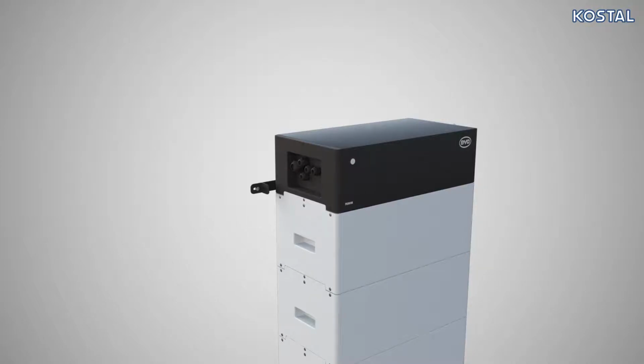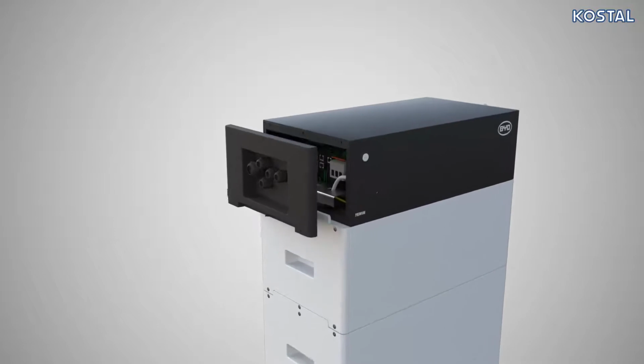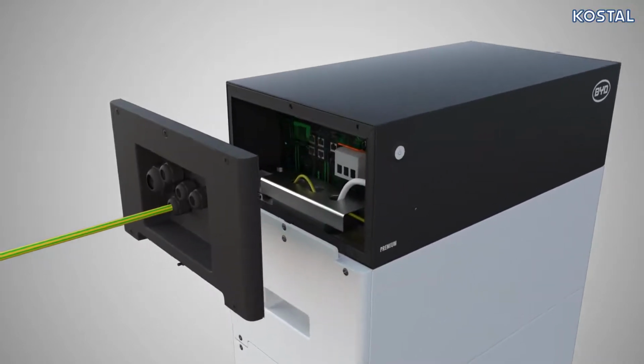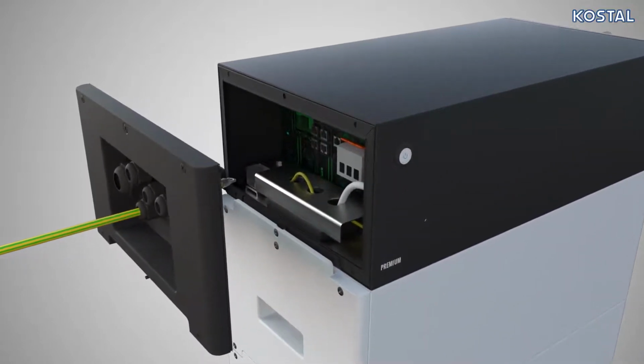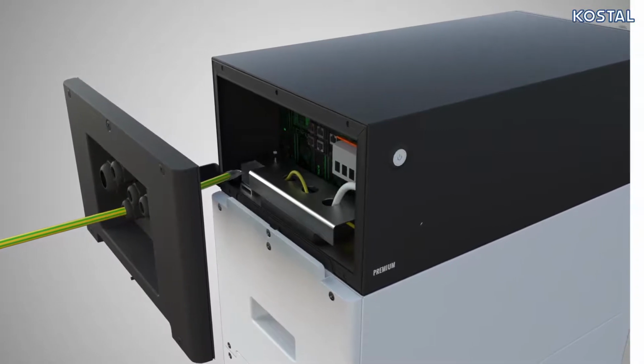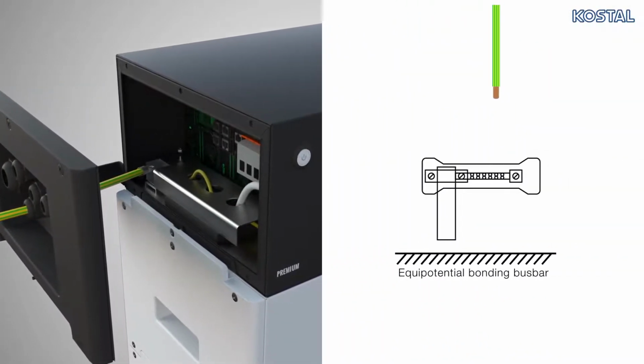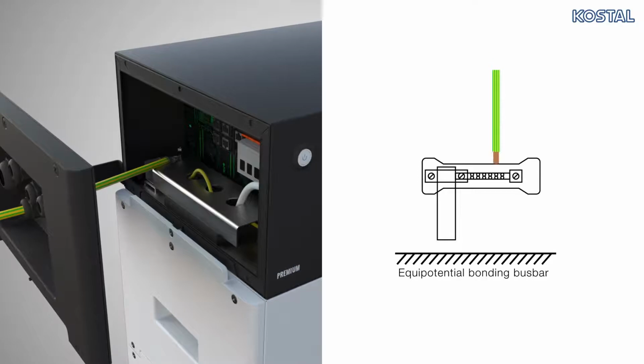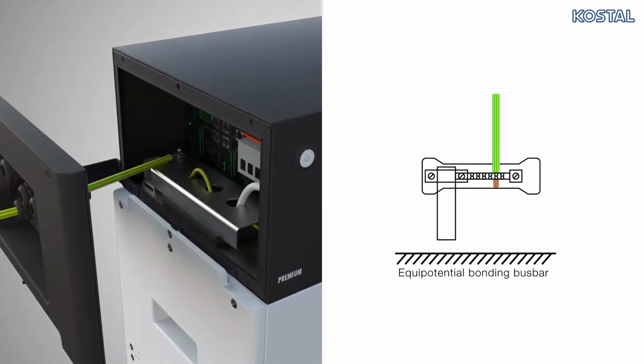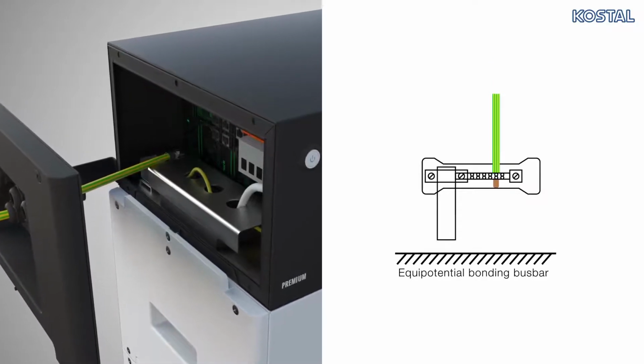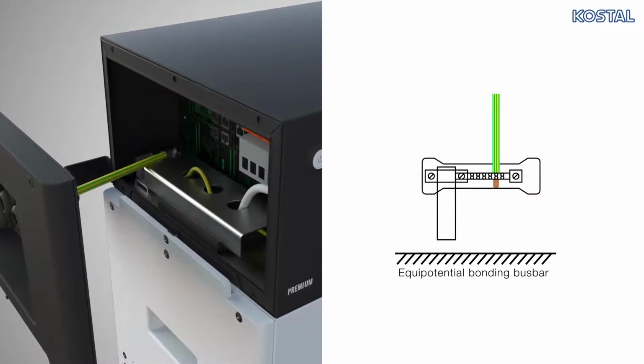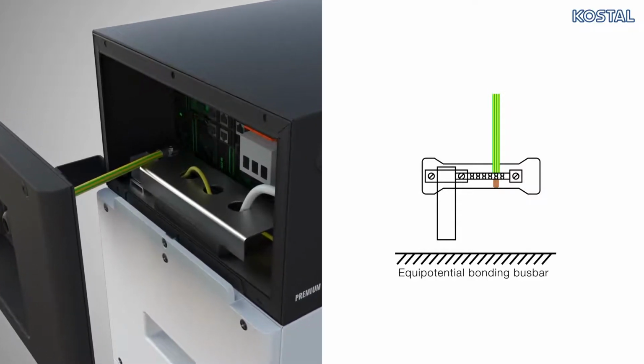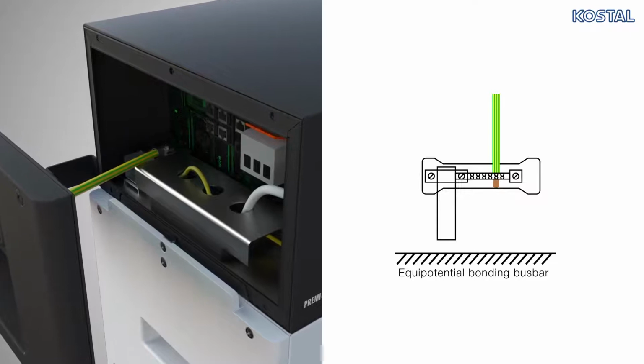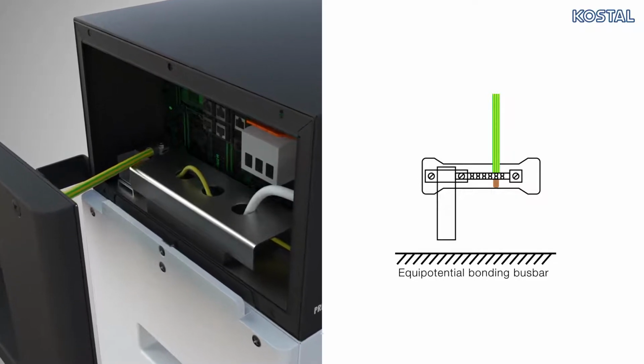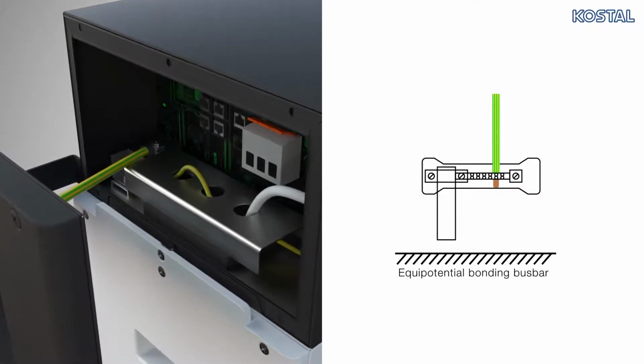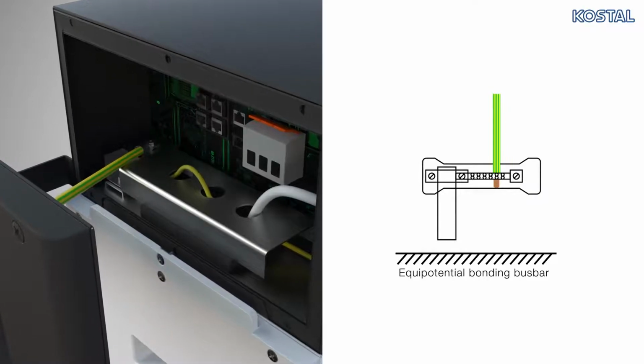Now guide the connection cables through the cable glands provided on the terminal compartment cover of the management module. Start by connecting the potential earth cable of the battery to the main earthing bus bar. Note: it is absolutely essential that this connection is made. There must be no potential difference between the PE connection of the PIKO MP Plus and the battery. Be particularly careful to ensure that all cables are installed and routed in an EMC-appropriate manner.